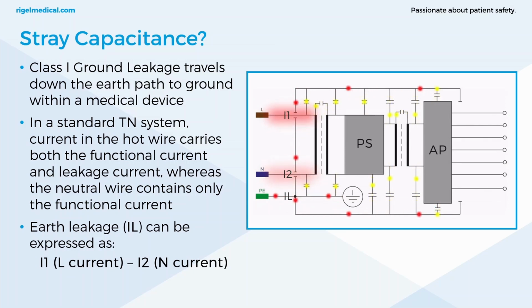Stray capacitance. Class 1 earth leakage travels down the earth path, ground path to earth within a medical device. In a standard TN system, current in the live or hot wire carries both the functional current and the leakage current, whereas a neutral wire only contains the functional current. Earth leakage can actually be expressed as the live current or hot current minus the neutral current.